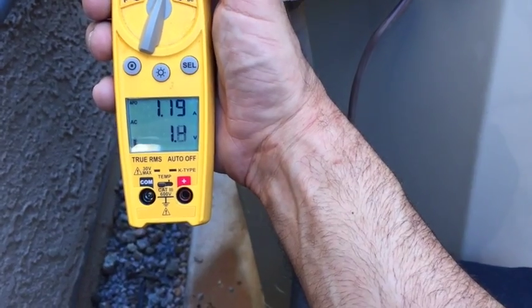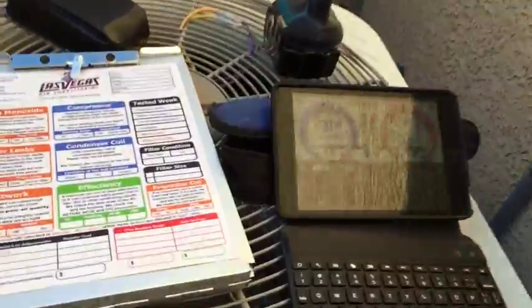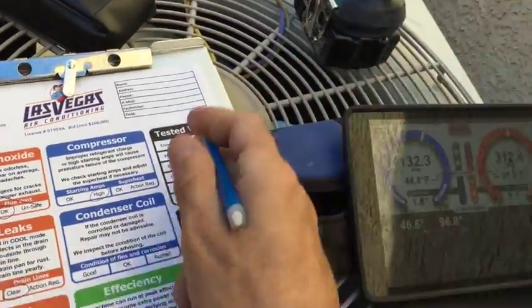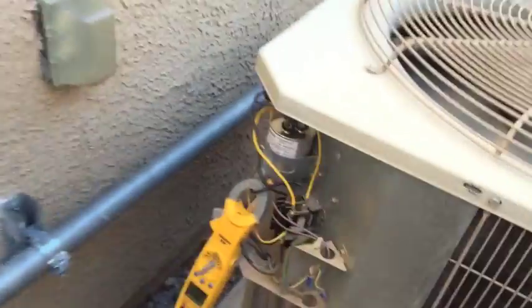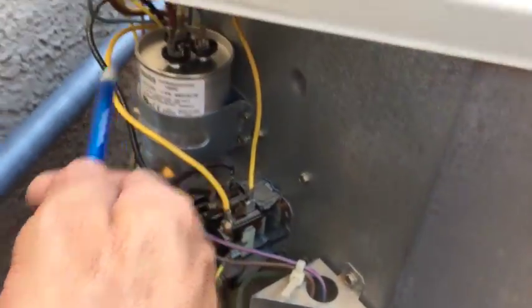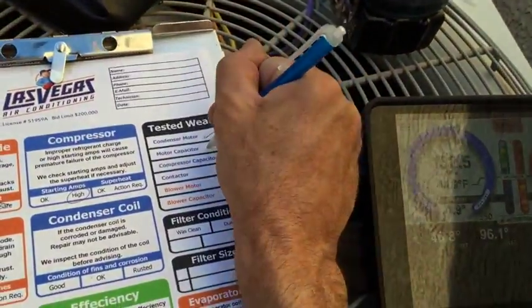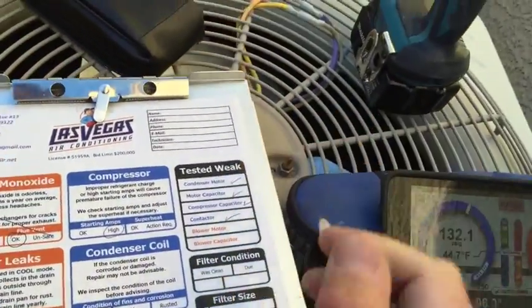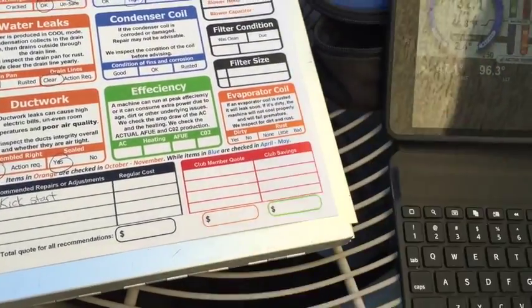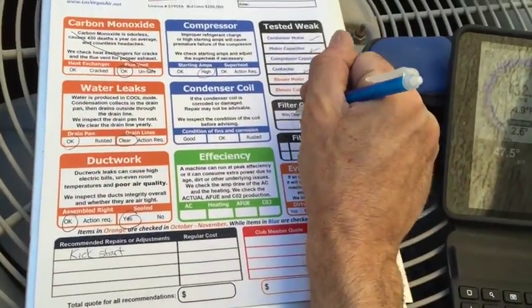So we're going to check the amp draw on the condenser motor here. Condenser motor's pulling 1.19, 1.18. It's rated at 1.4. So our condenser motor's okay. The motor and compressor capacitor, we just replaced this. This one's brand new. So check. Contactor, it's good. We're going to be in the attic checking those next time. Filters are clean.